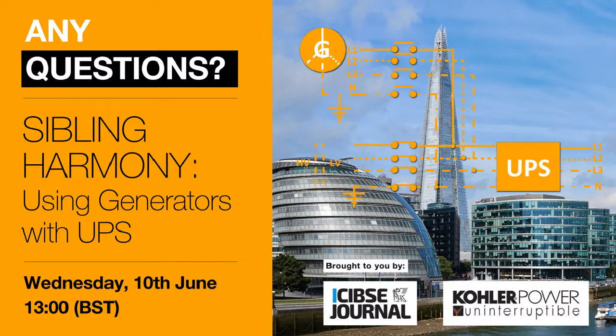This one's from Alice, and she asks, how quickly will the generator respond to a mains failure? Okay, well, I can take that straight away. That all depends on how quick we want it to respond. Like I was saying in the presentation, we typically delay the startup of a generator to make sure that the outage is real. Generators can respond and start up very quickly, in seconds, depending on the size. But typically, we will slow that down and make sure the outage is real before we bring the generator on, because we don't want it starting and stopping unnecessarily. So I hope that helps.